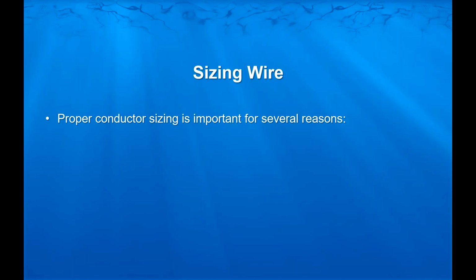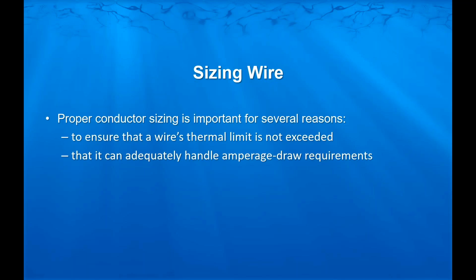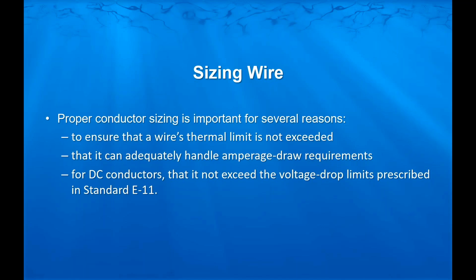So proper conductor sizing is important for several reasons. We need to ensure that we're not going to exceed the wire's thermal limit that it's rated for, that it can adequately handle the amperage draw requirement that we're going to ask it to handle. And for DC conductors, that wire does not exceed the voltage drop limits prescribed in standard E11, which we will address shortly.